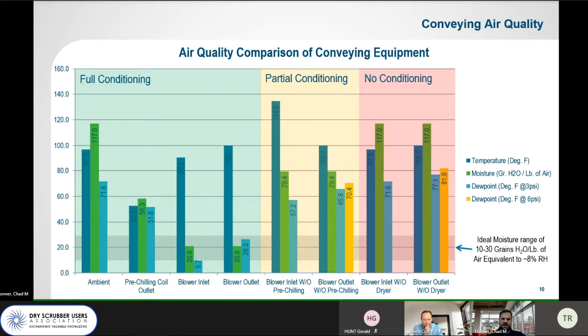So I've compared the different drying technologies. Full conditioning is what I consider pre-chilling the air, coupled with a desiccant dryer. Partial conditioning is a desiccant dryer only, and I also compared that to no conditioning at all. On full conditioning, we get down to low single digits of dew point, and about 20 grains of moisture per pound of air.